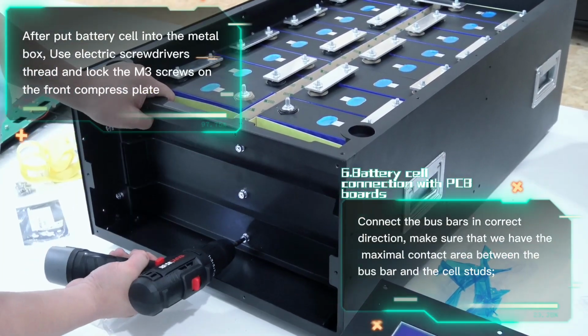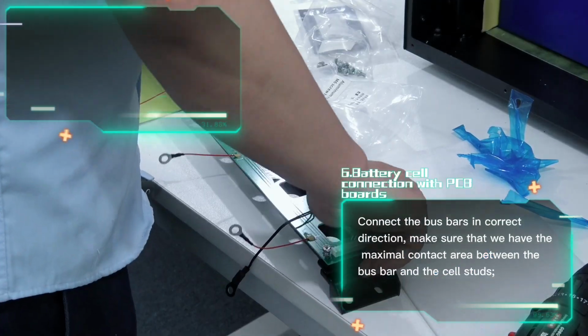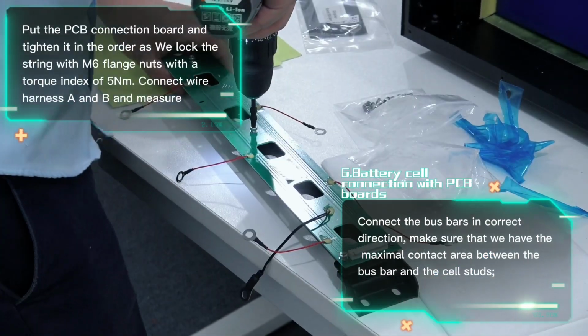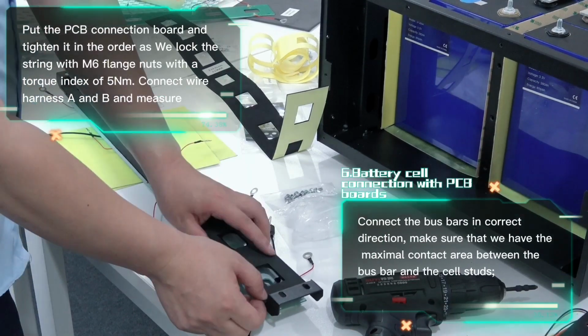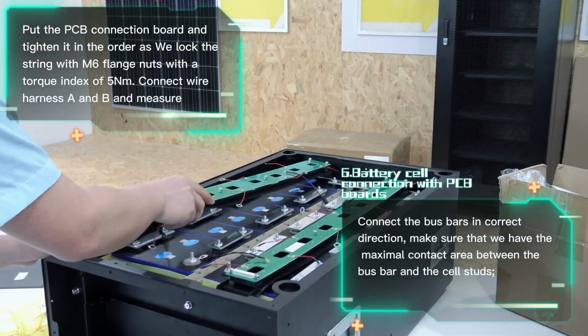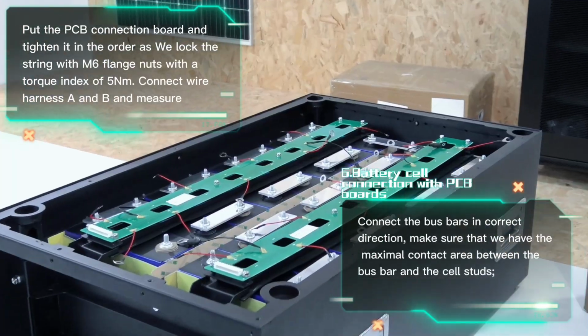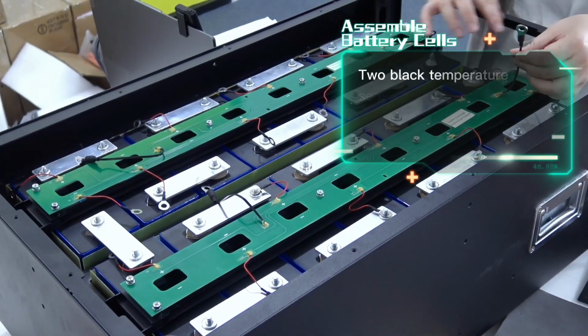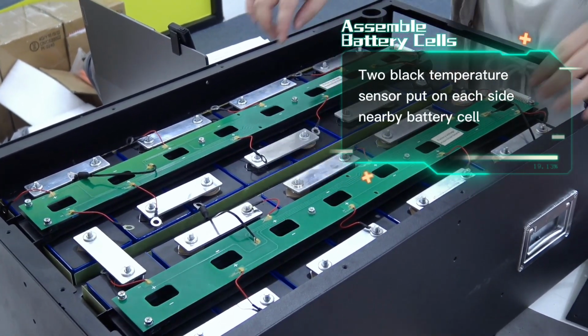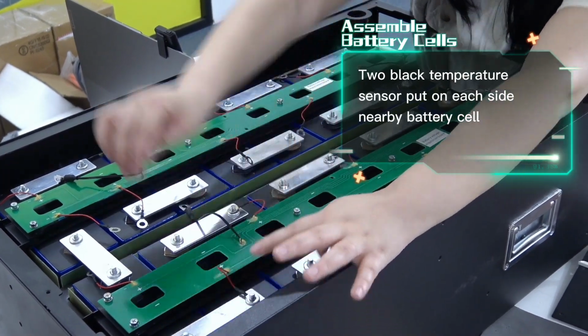Compress the PCB connection board and tighten it, lock the string with M6 flange nuts with a torque index of 5 Nm. Connect wire harness A and B and make sure each PCB board has 2 temperature sensors, which can be displayed on the software to confirm the battery status.